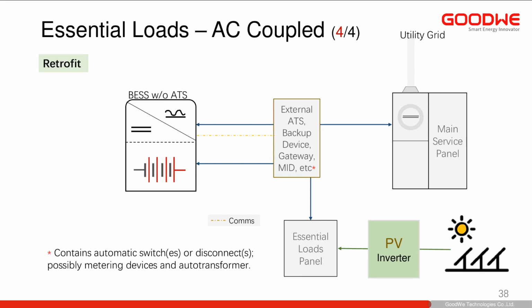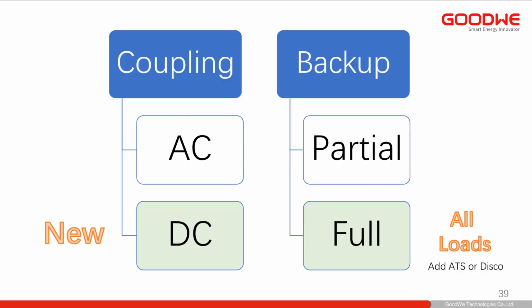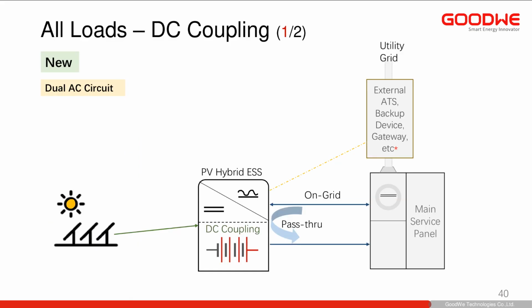And we also have the same sort of setup, but we have the external ATS again, right? So that's another possibility. Now we get on to full loads, new installs. Here we have to have a way of disconnecting from the main service panel. So that's our external ATS between the main service panel and utility grid, or MID device. And we have to have communications to it because the ESS is in charge generally. So it actually is saying when to make these transfers.